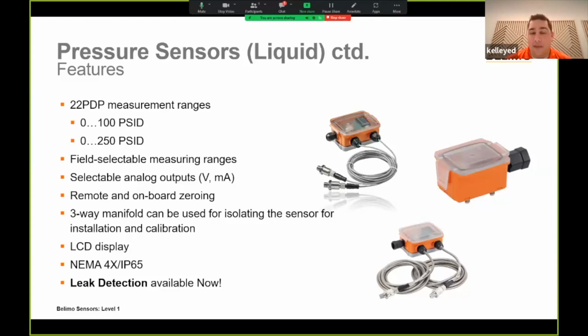We launched these in December or November of last year, so these are fresh. The image on the top right here is differential pressure for liquid as well. You'll see they come with remote probes, so they're much easier to install. We do offer three-way manifolds with these as an accessory as well, if needed. You'll notice with that one on the top, it comes with an LCD display. There's a zeroing button, or you can remote in and zero it out from the BMS system.